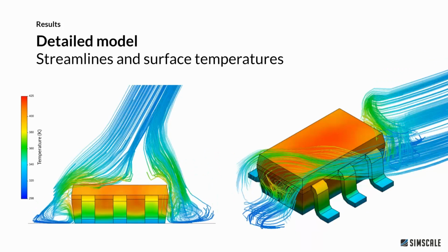So that's something to keep in mind when you're actually doing your CFD calculations. You can't necessarily be drawing conclusions about the surface temperatures when you're doing this resistance modelling. And that's important if you're comparing it to a thermal image.